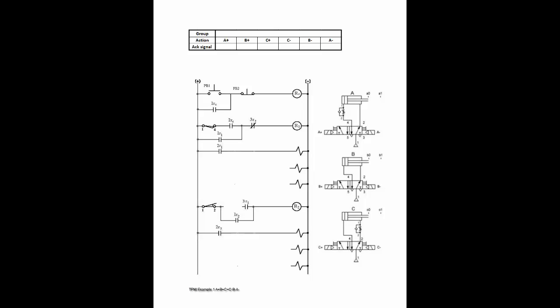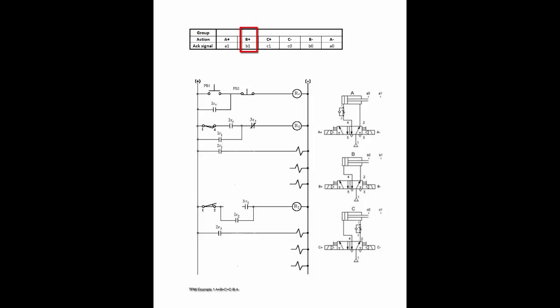With the initial positions of the three cylinders shown on the template, next enter the corresponding acknowledged signals. A plus will trigger A1 when cylinder A is fully extended. B plus triggers B1. C plus triggers C1. Similarly, C minus triggers C0 when cylinder C is fully retracted. B minus triggers B0. A minus triggers A0.